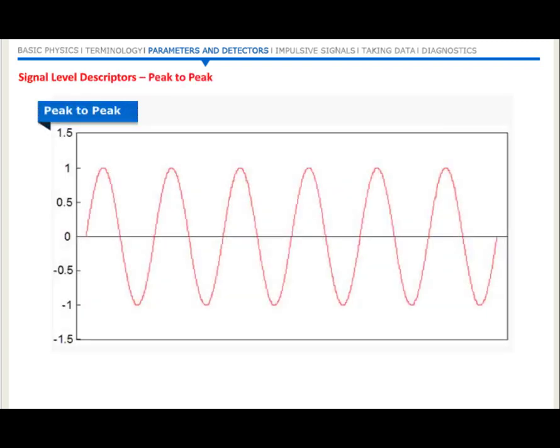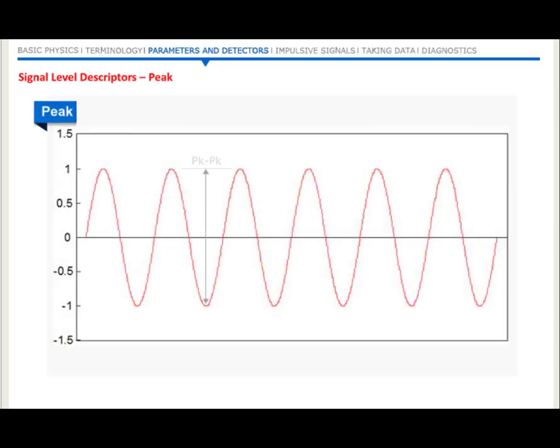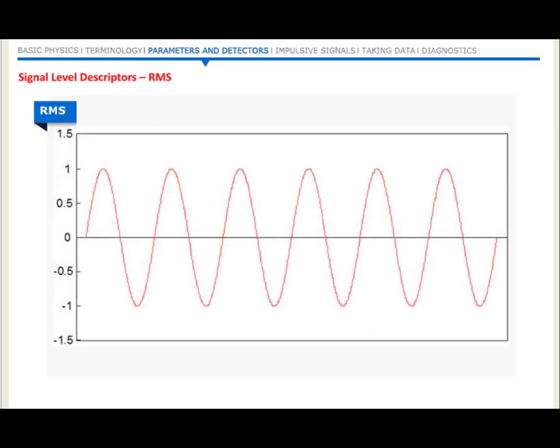1. The total signal value from one extreme to the other extreme is called peak to peak, pk to pk. If the peak-to-peak amplitude is not constant, that is, changing with time, we usually record the value when it was at its biggest or maximum. 2. The signal value from point of rest or reference position to one side only is the peak value. 3. Most ISO and European standards will require you to measure the signal's root mean squared value, RMS. The RMS value is the most commonly used way of expressing the value.